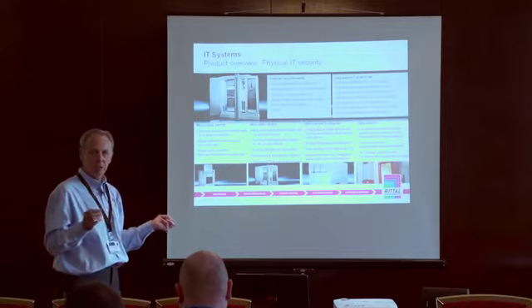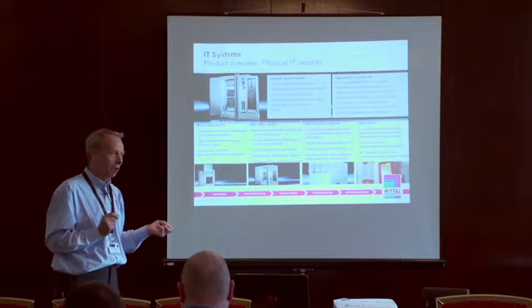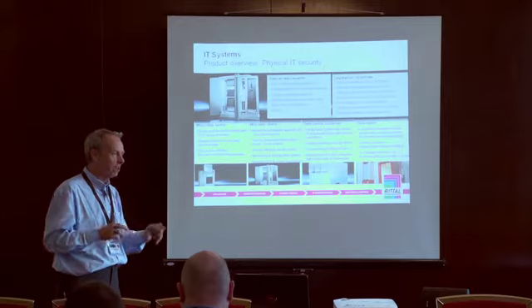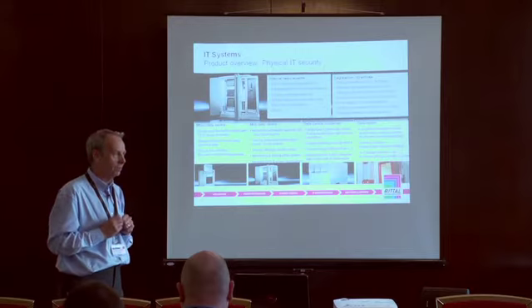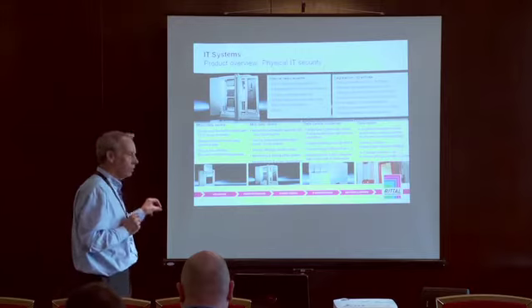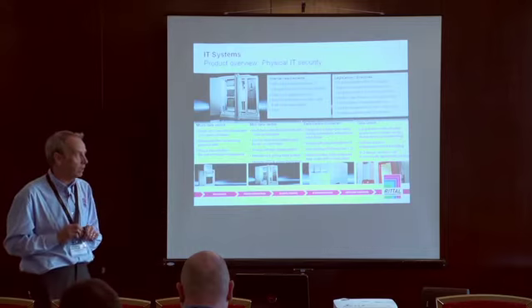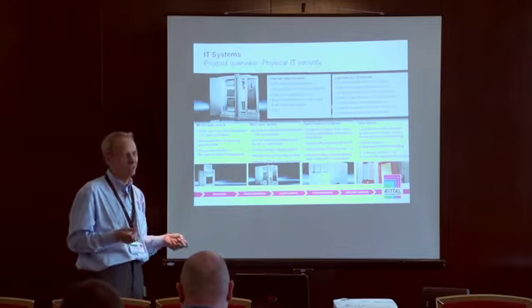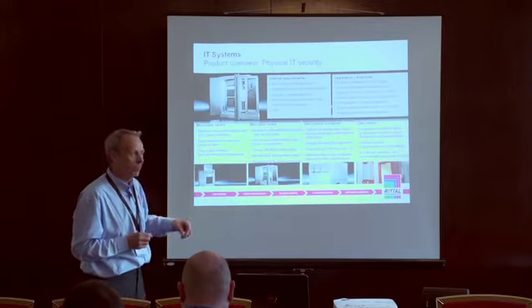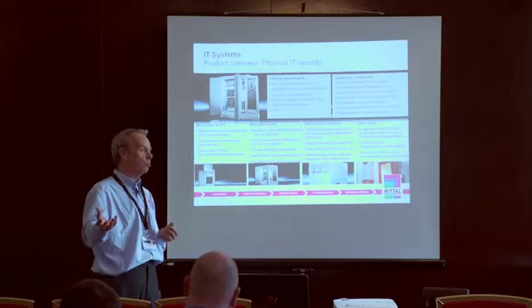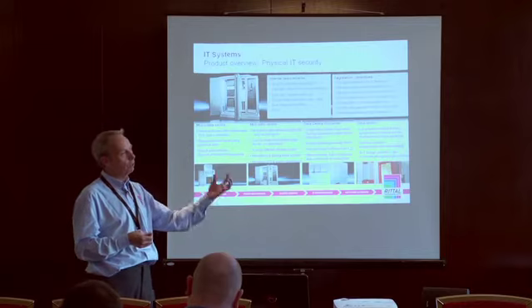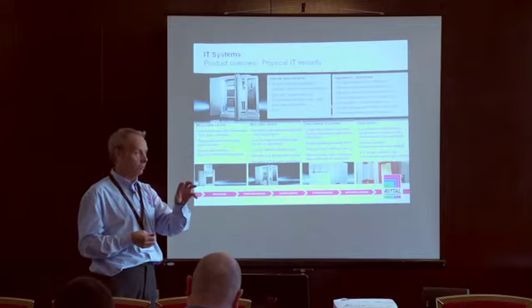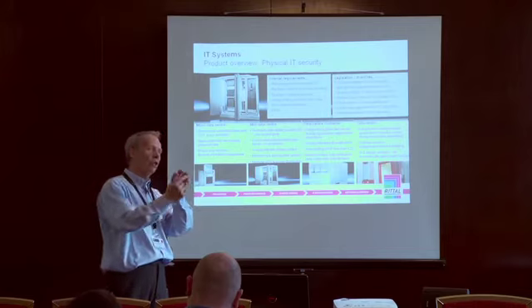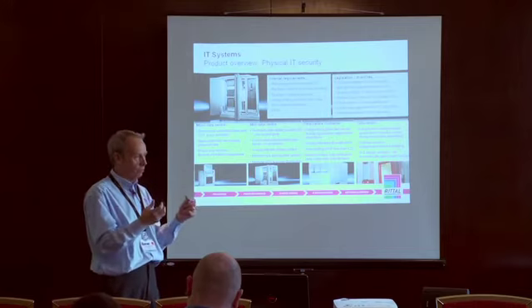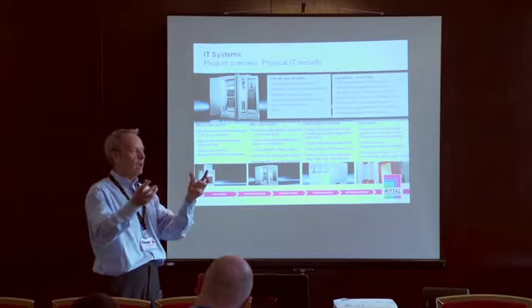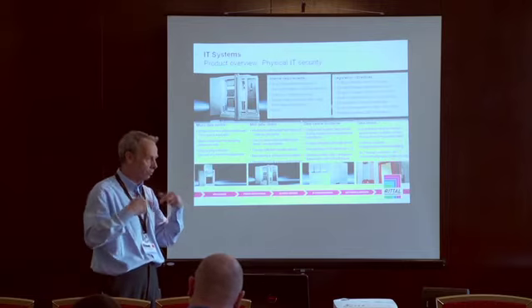So we were talking earlier, before some of you arrived, about water solutions and people getting a bit twitchy about water in the computer room. We actually do a high density cooling solution, which our friends at HP mirror exactly what we do, because it's ours anyway, but there we go, which is water based. So you have chilled water going into an enclosure, fans blow the cold air onto your servers. The servers' motion is to drag that cold air through the servers, and when the cold air gets to the back, it's then sucked back out again, and it just goes through the loop again.